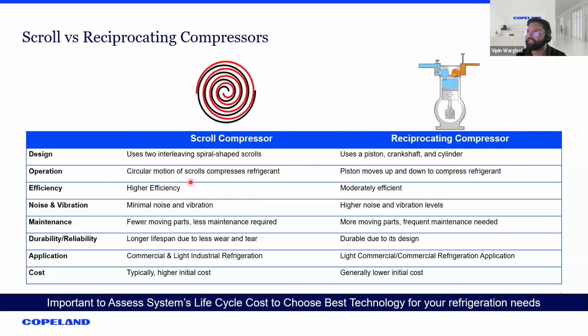So the scroll would have a circular motion, and the reciprocating will have a piston which is moving up and down to compress the refrigerant. If you talk about the efficiency, the scroll compressors have relatively higher efficiency because of their higher volumetric efficiency, and the reciprocating compressor has a moderate level of efficiency. As for noise and vibration, because scroll has relatively fewer moving parts, scroll compressors would produce relatively less noise and vibration, while reciprocating would have higher noise and vibration levels.